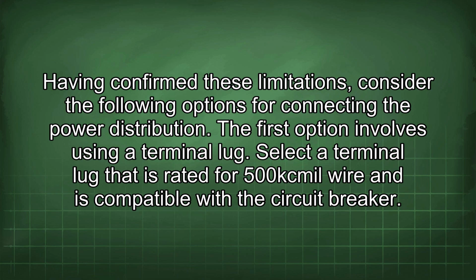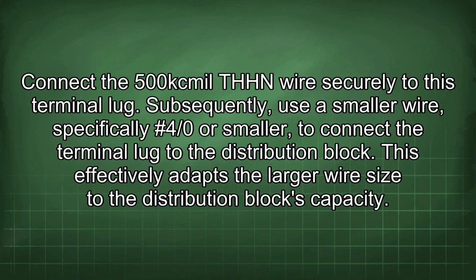First option involves using a terminal lug. Select a terminal lug that is rated for 500 kcmil wire and is compatible with the circuit breaker. Connect the 500 kcmil THHN wire securely to this terminal lug. Subsequently, use a smaller wire, specifically #4/0 or smaller, to connect the terminal lug to the distribution block. This effectively adapts the larger wire size to the distribution block's capacity.